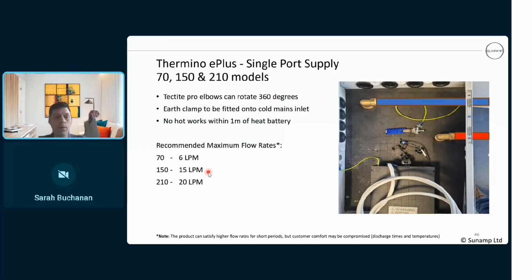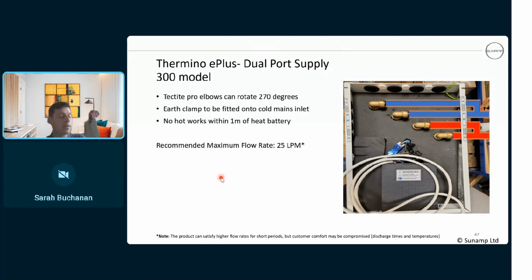I had another job, a 150, fitted down in Liverpool. The installer went AWOL, so we couldn't get in touch with the installer. So I had to go down. The customer was only getting about 2 inches of hot water coming out of their bath. So I drove down to Liverpool and found that the flow rate was up at about 28 litres per minute, almost twice what it was meant to be. So we stuck a valve in the outlet of the TMV just to restrict that down to 15. We've never heard back from the customer. This is all part of the commissioning that you should be doing on site. So just bear it in mind.